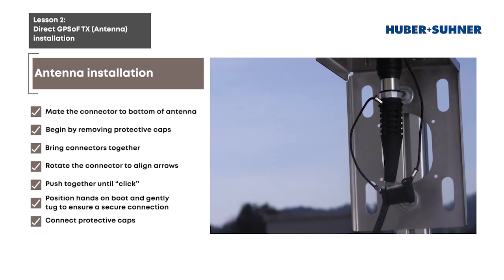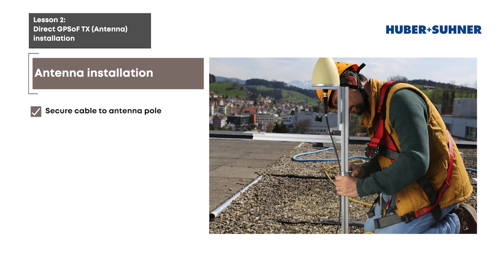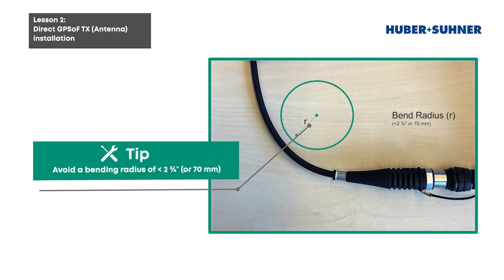Finally, using a fiber optic cable clamp, secure the fiber optic cable to the antenna pole, being careful to not use too much force. Too much pressure applied to the cable or bending the cable with a radius of 2 3/4 inches or 70 millimeters or less may potentially affect performance. For specific details, please refer to the installation manual.